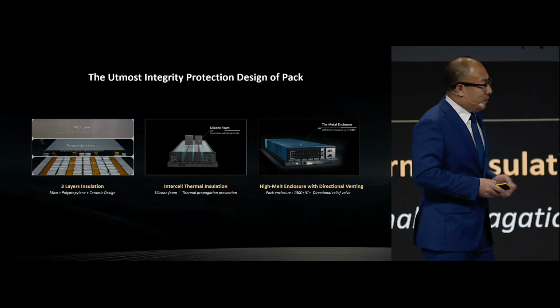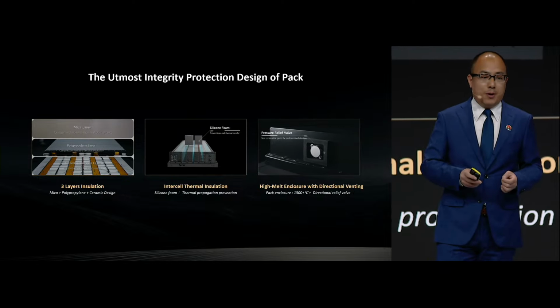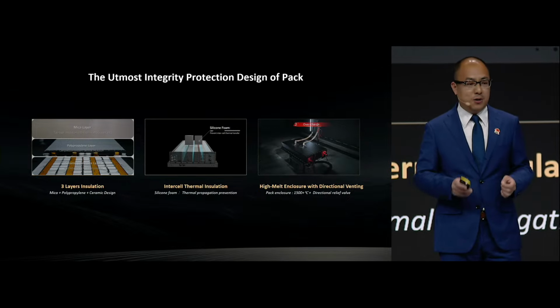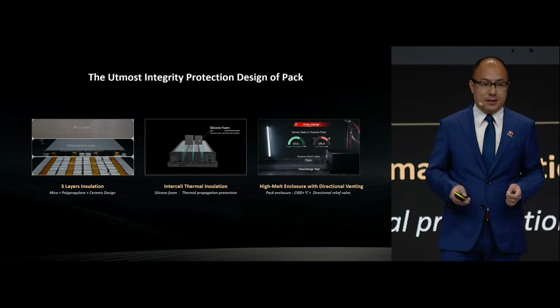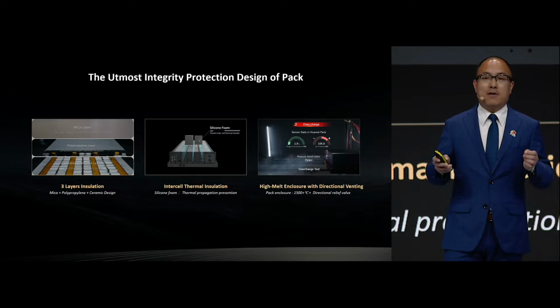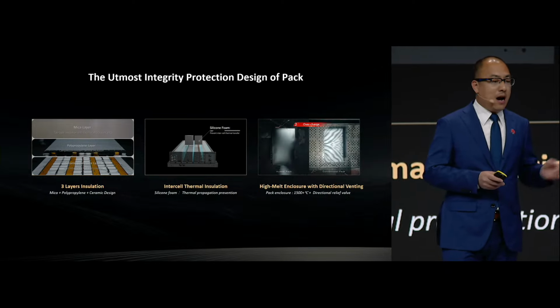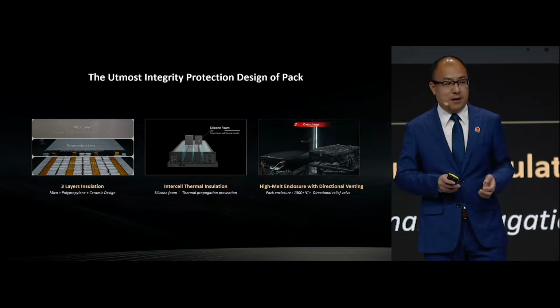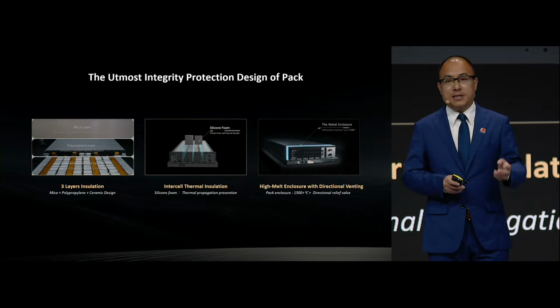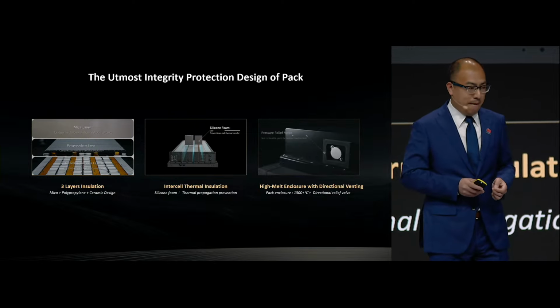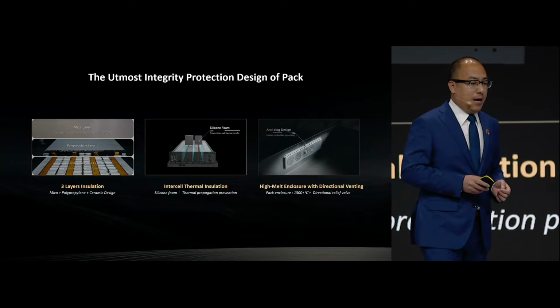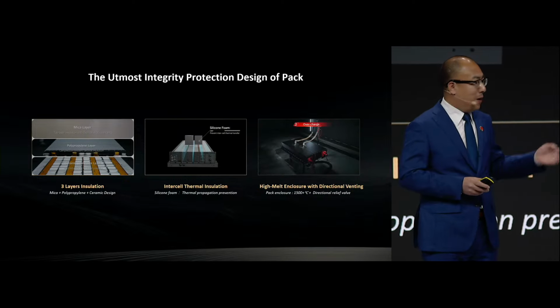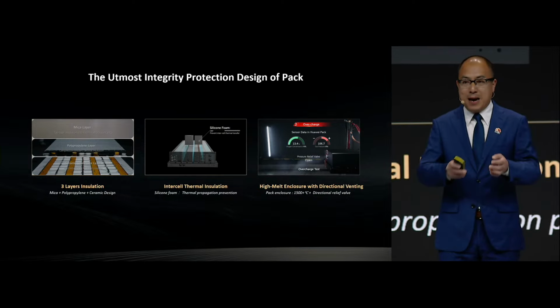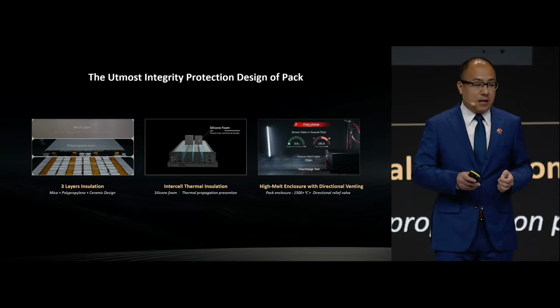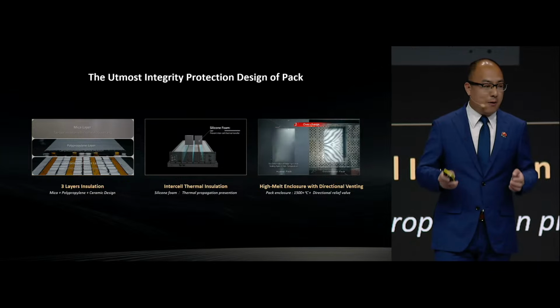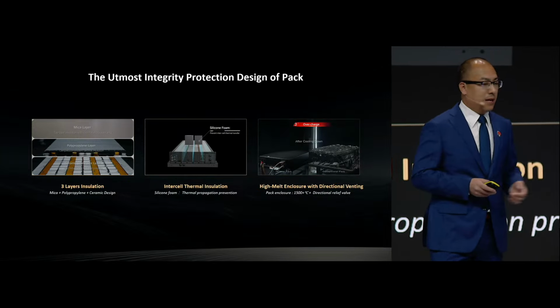And the third one, the pack is built with a zinc steel enclosure, and the melting point exceeds 1,500 degrees Celsius, higher than the temperature of cell thermal runaway, which is 600 degrees Celsius. Additionally, we have innovatively added a pressure relief valve on the back of the pack. Combustible gas can be directly transferred to the outside.